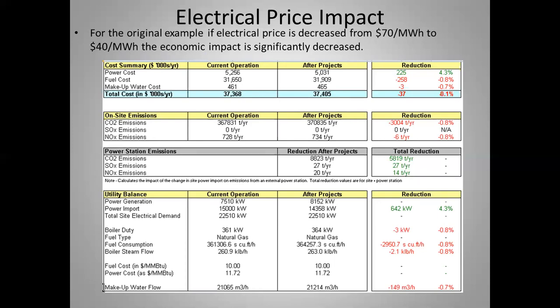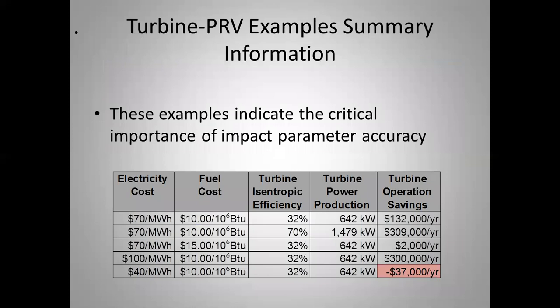Decreasing electricity price to $40/MWh with fuel at $10 results in a $37,000 loss — you definitely wouldn't do this with expensive gas and cheap electricity. Summarizing the cases: all used 32% isentropic efficiency except the second case at 70%, which showed its large impact. The other scenarios varied fuel price and electrical cost, demonstrating how sensitive the economics are to these parameters.